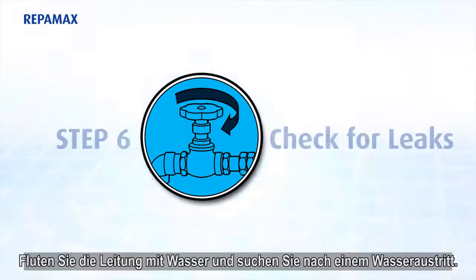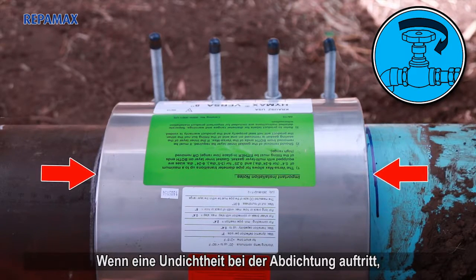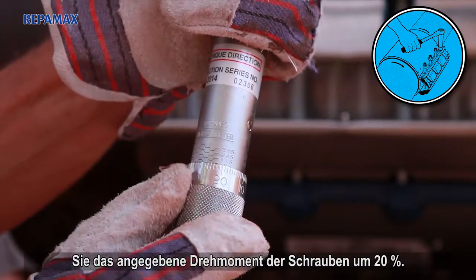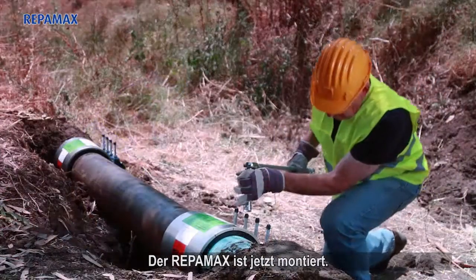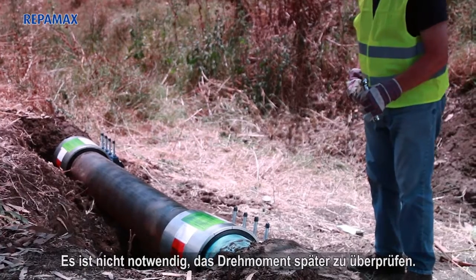Step 6: Recharge the line and check for leaks. If any leakage across the seal end is evident, reduce the pressure in the line and increase the labeled torque of the bolts by 20%. The Repamax is now installed. There is no need to recheck the torque later on.